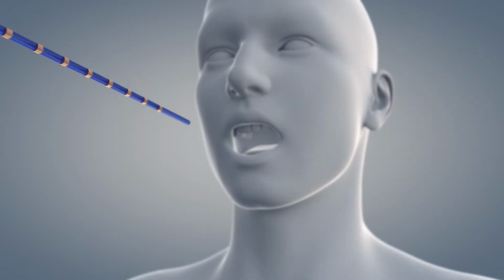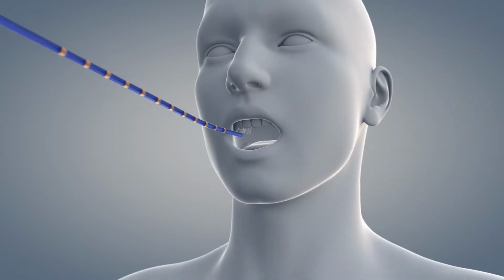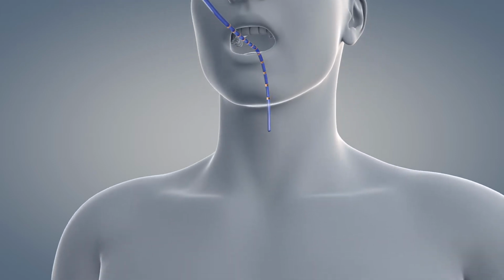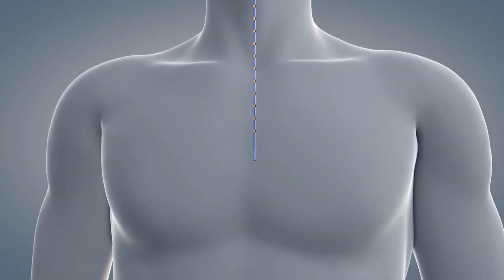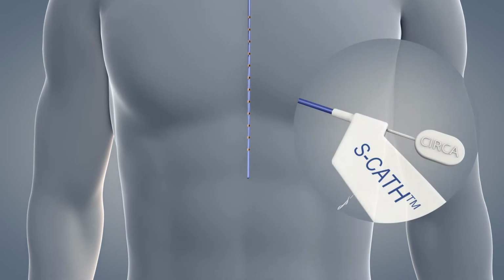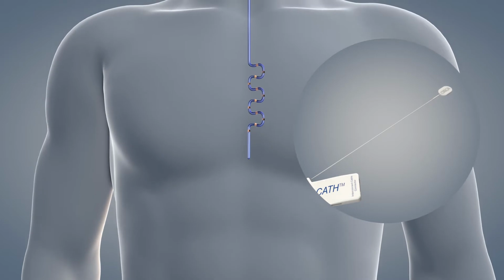Under fluoroscopic guidance, advance the probe into the distal esophagus until the distal tip is approximately 1 centimeter superior to the gastroesophageal junction. Once the probe is properly placed, grasp the connector housing of the probe with one hand and with the other hand grasp the end of the stylet and remove it completely. The probe will shorten as the stylet is removed. Do not reinsert or advance the stylet while the probe is in the esophagus.